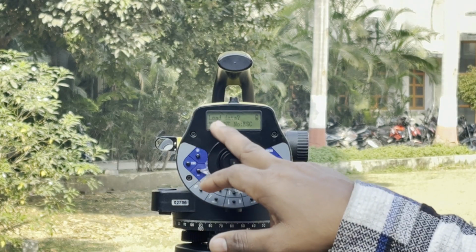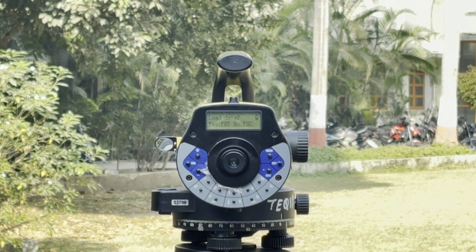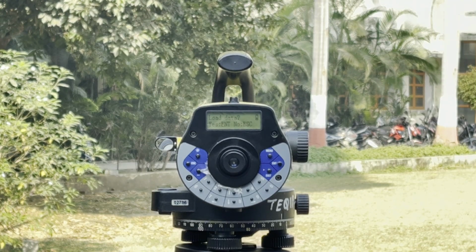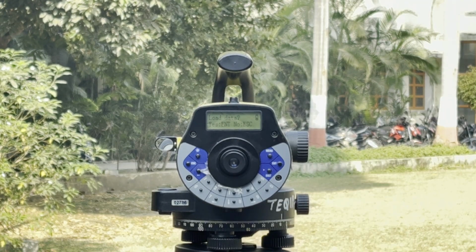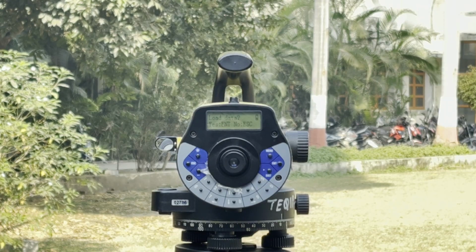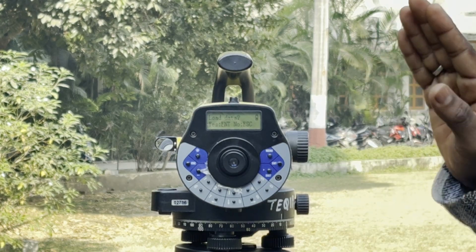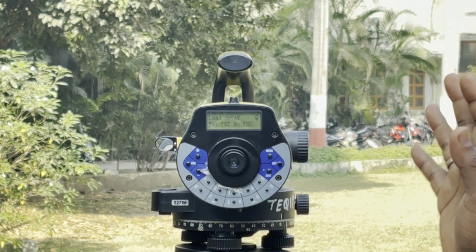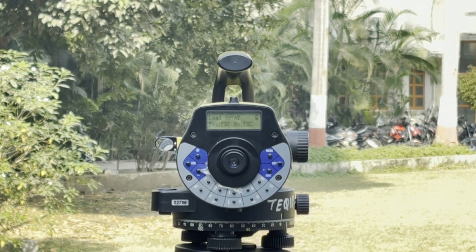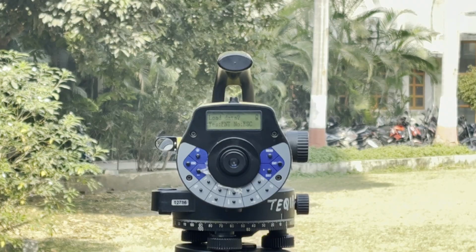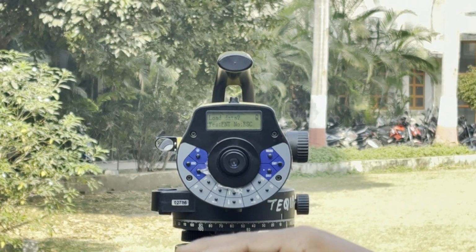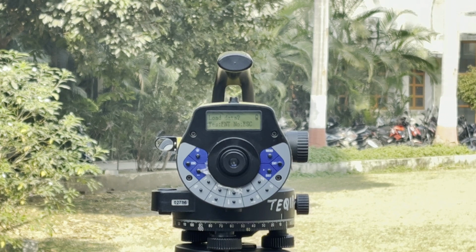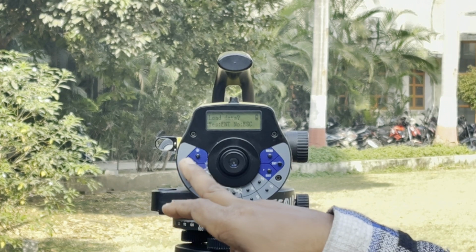Now the instrument asks to load the data. If you have data already and we are changing location and performing the same practical, like I entered 1301 as the job name, and now I shift my instrument to another location, then I have previously loaded data under a job name. So simply you need to enter the same job name, and then you can click on the yes button to load the data. Right now we haven't any data. Okay, right now I am escaping.